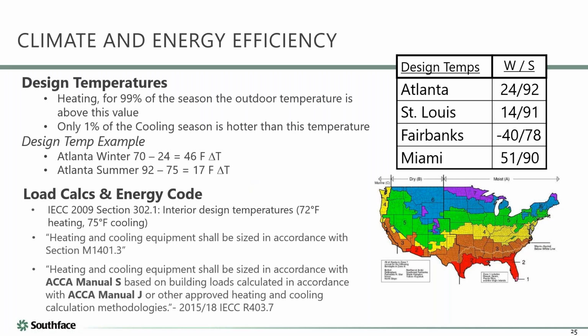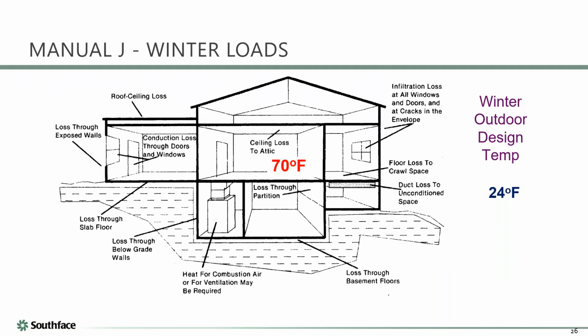So it's that UA delta T calculation that we talked about in some earlier webinars. And I think that's probably enough said on that. So in essence, here's what happens in a winter load calc. We do it at nighttime, so we're going to get 0 solar gain. We absolutely ignore all of the interior gain from appliances. So this is a really worst case scenario. And we do UA delta T heat loss through the walls, the windows, the doors, the floor, the ceiling. We add something for the leakage of the house. We account for the ducts, and we add it all up, and that adds up to be, let's say, 37,252 BTUs per hour. And our job then is to select, let's say, a furnace that will be able to deliver at least 37,252 BTUs an hour. That's how it works.